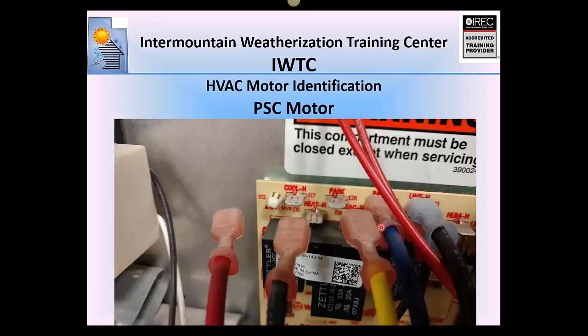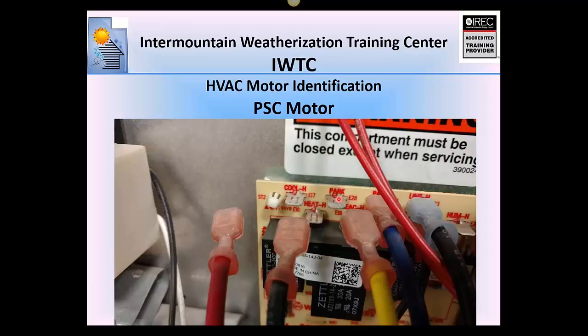The speed leads always connect to pins on the circuit board. In this example the board is marked cool, heat, park, and park. Red is on cool (high speed) and black is on heat (low speed). The park terminals are dead terminals — just somewhere to park unused wires so they don't hang loose and short out. You can swap leads around to change the speed for cooling or heating.